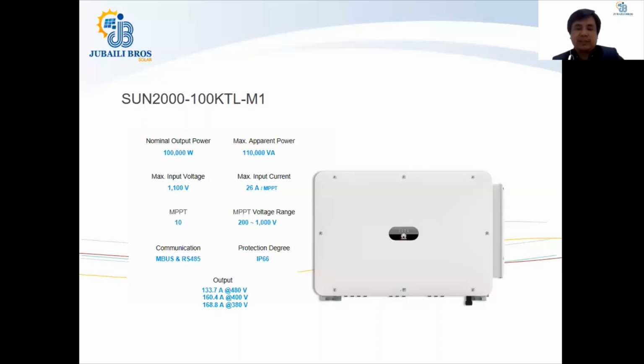The output of this inverter comes in 480 volt, 400 and 380 volt. So we have two versions of these inverters. One is the low voltage 380 400 volt and the other version is 480 volt. Similarly, with the 60 kilowatt inverter, we have two versions, the 400 and the 480 volt. Huawei is making two different versions because in many scenarios you would have a small PV project getting terminated to the MV system, and you do not want to use high voltage switch gears. So you can still use the 480 volt Huawei inverter with the normal conventional switch gear available in the market, and have the benefit of the 480 volt inverter, which is better in terms of output generation, the duration, and saves you cost on the cables, because for the 480 volt, the inverter doesn't have a neutral cable requirement.